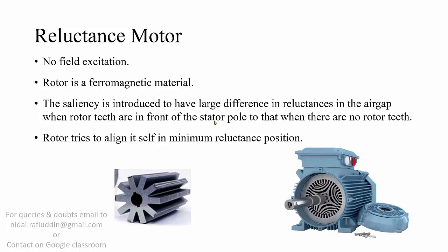The saliency in the rotor is introduced in order to have a large difference in reluctances in the air gap: when the rotor teeth are in front of the stator pole versus when the rotor is oriented such that there are no rotor teeth in front of the stator pole. That is, the rotor tries to align itself in the minimum reluctance position. Shown here are the two types of rotor of the reluctance motor. The rotor design in figure 2 allows minimum reluctance, meaning it allows magnetic flux lines to pass through most easily.